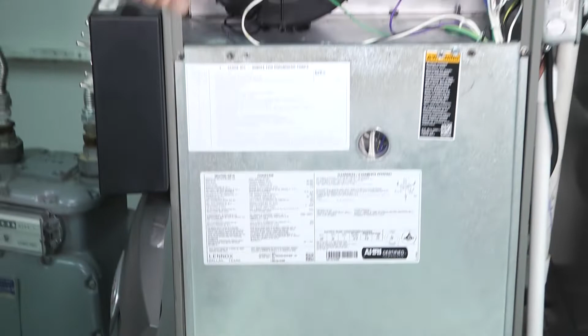Now, as we go through here, we check some different things out. We're going to check amp draws on our motors. We have an inducer motor and a blower motor in here. We want to check an amp draw on the motor. The reason why we need to check that amp draw is we need to make sure that our motors are operating within tolerance. If that amperage gets too high, we could compromise the integrity of those motor windings, and the windings inside may burn up, lock up, seize up, and then our motor is not working anymore, and then there's a problem overall.